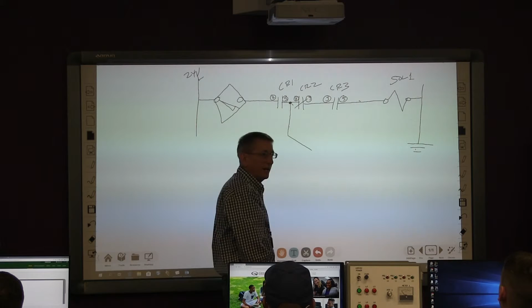Don't just go up and probe randomly, right on the edge of the panel like it's not doing anything - you're just wasting time. And you get all kinds of weird voltage readings too, don't you - like 60 volts, 30 volts, and you wonder where that's coming from. I've seen guys do it, with a meter in the panel just probing around like that.